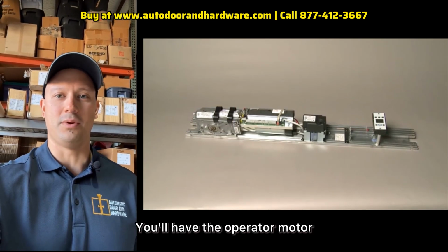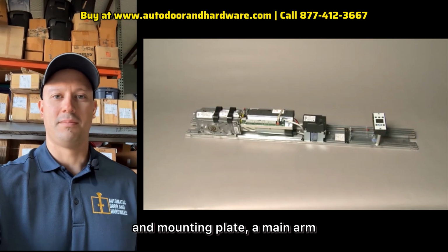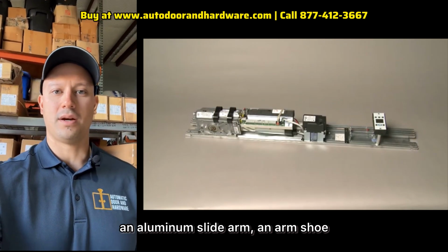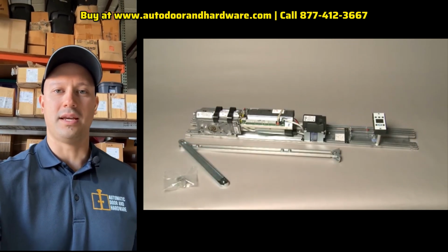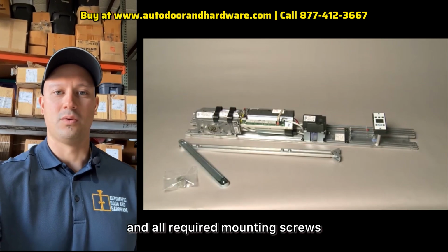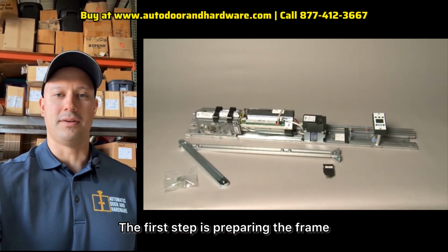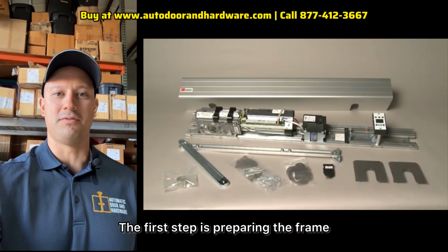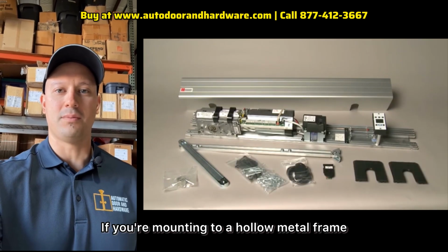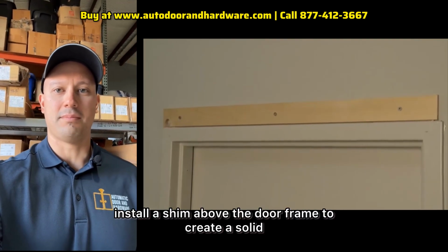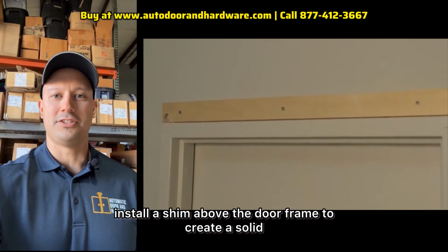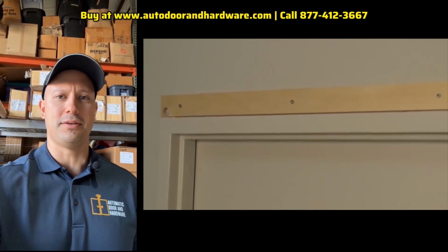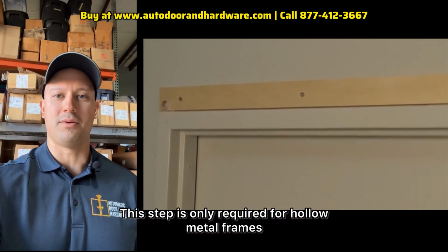You'll have the operator motor and mounting plate, a main arm, an aluminum slide arm, an arm shoe, an on-off switch, an aluminum cover, and all required mounting screws. The first step is preparing the frame. If you're mounting to a hollow metal frame, install a shim above the door frame to create a solid, level mounting surface. This step is only required for hollow metal frames.